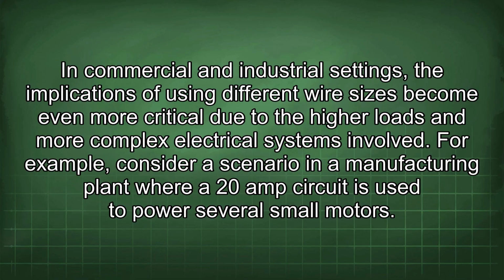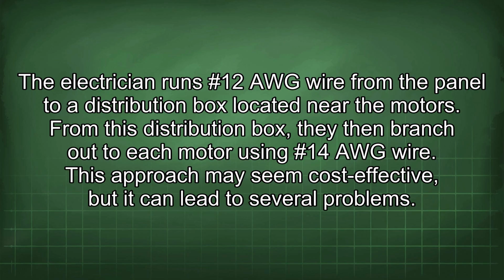In commercial and industrial settings, the implications of using different wire sizes become even more critical due to the higher loads and more complex electrical systems involved. For example, consider a scenario in a manufacturing plant where a 20 amp circuit is used to power several small motors. The electrician runs #12 AWG wire from the panel to a distribution box located near the motors. From this distribution box, they then branch out to each motor using #14 AWG wire. This approach may seem cost-effective, but it can lead to several problems.